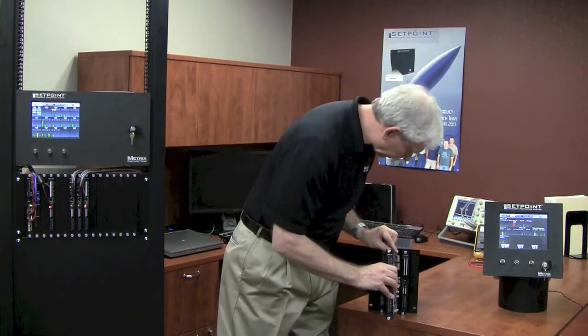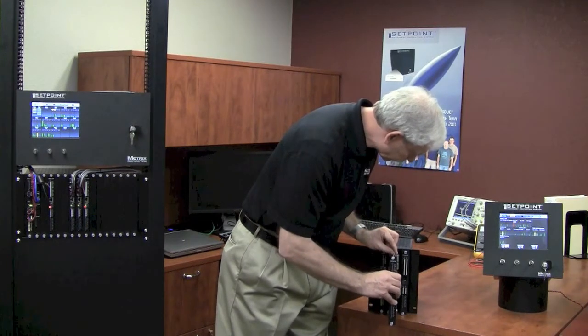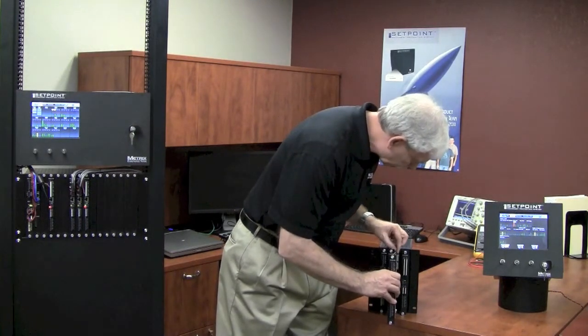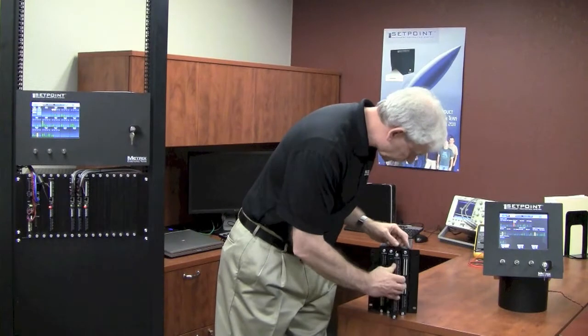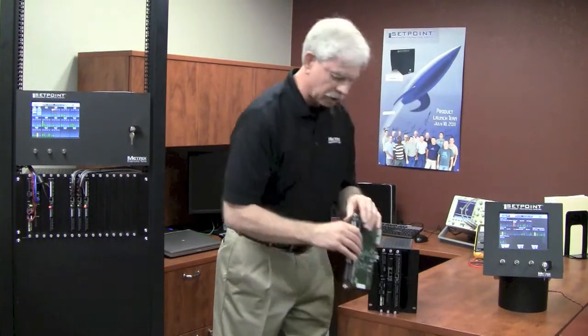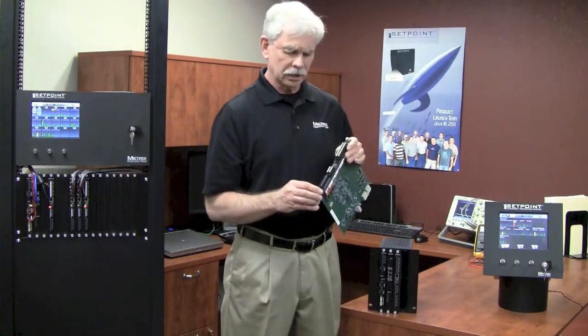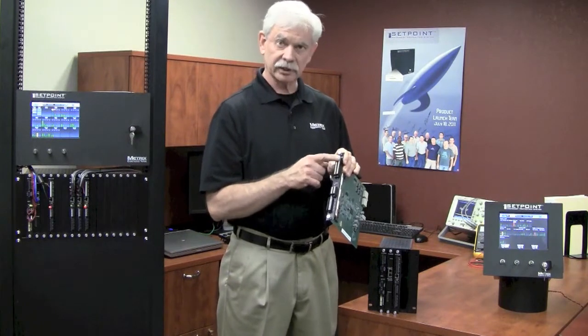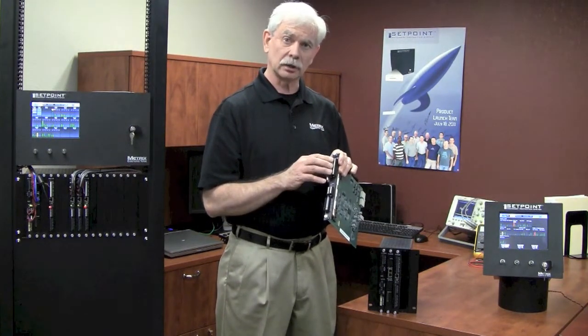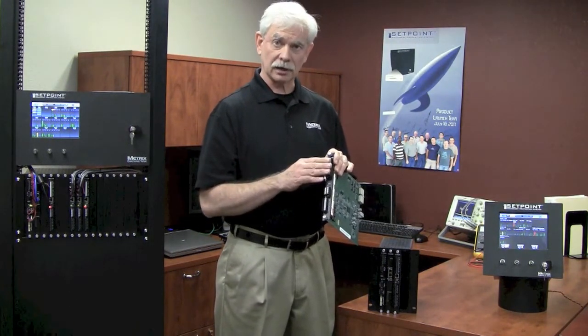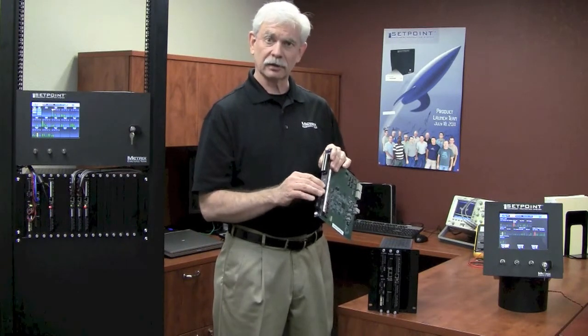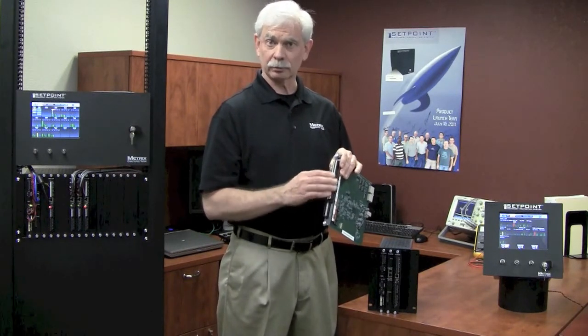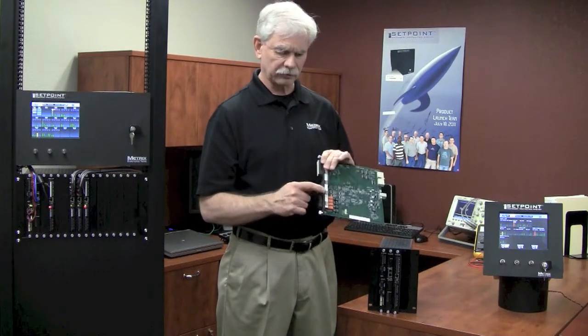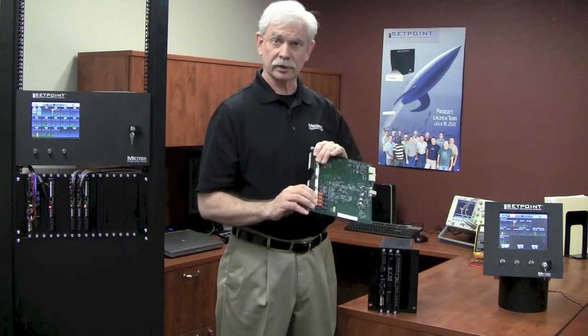The last module type we'll show you in the system is used for measuring temperature. And it is actually a six-channel card called the Temperature Monitoring Module, or TMM, and we have inputs for 6 different RTDs or thermocouples at the top here. In the middle we have our analog outputs, and there's 6 of them because we have 6 channels, and then we have 4 relays that are used.